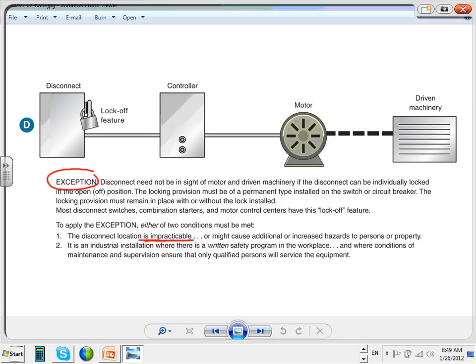How do you define impractical? It's dangerous. You don't have room. So impractical to put it. So the rule is you have to have the disconnect next to the equipment and the controller, 90% of the time. Or it might cause additional damage or increase hazard to personnel or property. You put a disconnect right next to a machine, guys, that is mixing chemical equipment. If somebody accidentally disconnected and it stopped this machine, you're going to have an explosion. You're going to have a big mess on you. You can imagine how you really need the disconnect isolated in one location where nobody, maintenance people, accidentally disconnects it. That becomes a big deal.